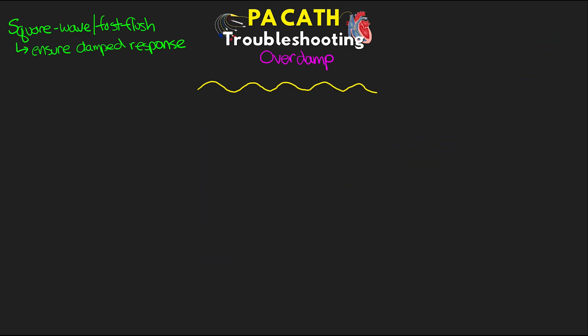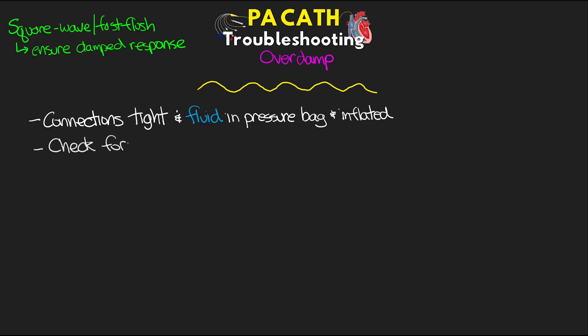If you do confirm that you are over-damped, make sure that all connections are tight and that there is enough fluid in the pressure bag and that it's appropriately inflated. Check for any air in the transducer or the pressure tubing. If air is present, you're going to need to remove it and ensure that you have a continuous flow of fluid.